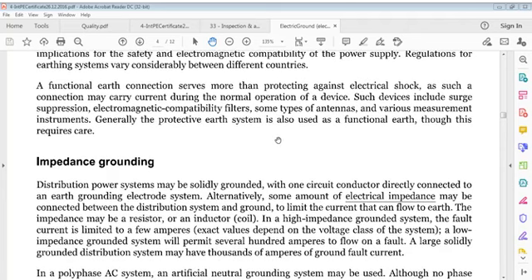A functional earth connection serves more than protecting against electrical shock. Such a connection may carry current during normal operation of a device. Such devices include surge suppression, electromagnetic compatibility filters, some types of antennas, and various measurement instruments. Generally, a protective earth system is also used as a functional earth, though this requires care.